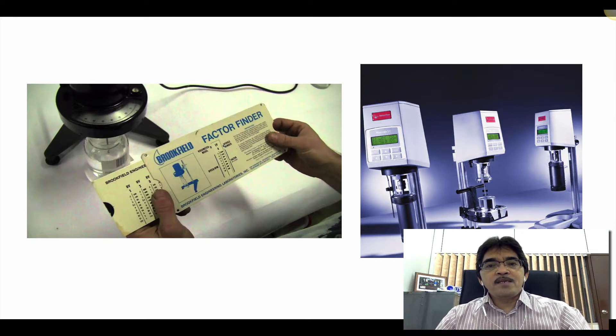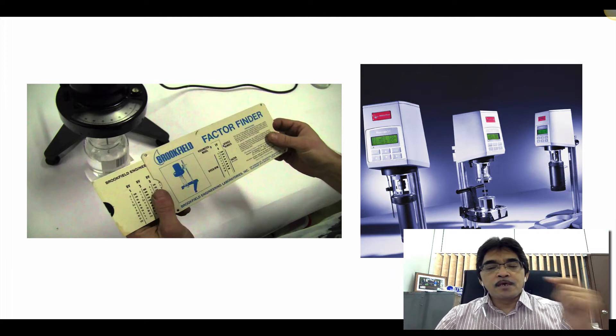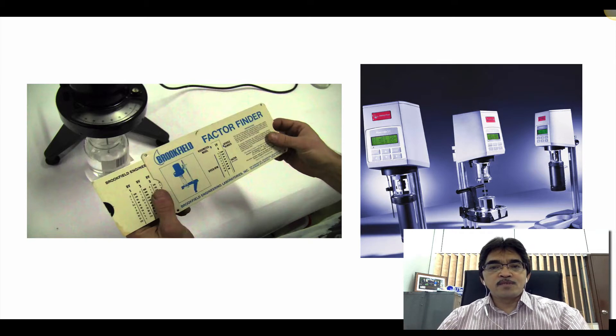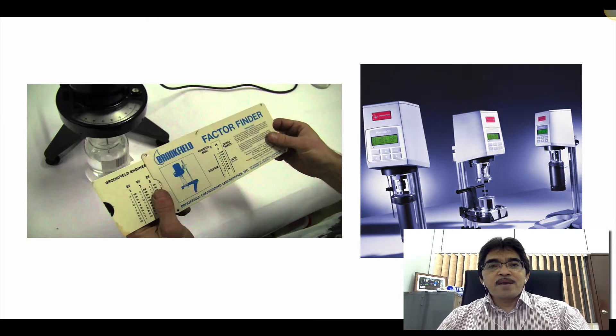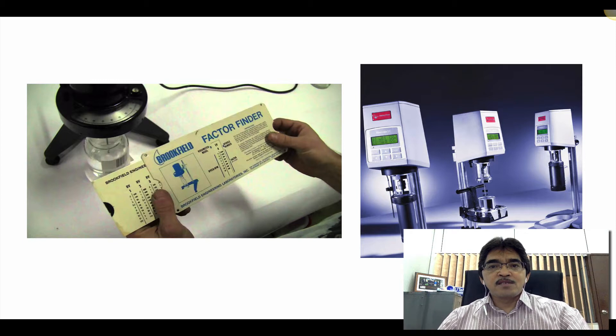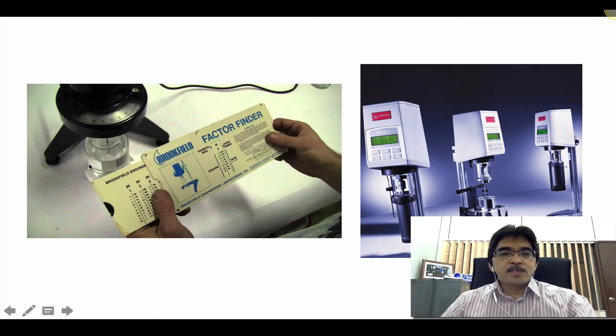We have many different ways of measuring viscosity. We can use a simple empirical method, for example, we can use the consistometer, where we measure time when we let the sample flow, then we can use a conversion factor to change that to a kinematic viscosity. Or we can use a capillary glass viscometer. That is an empirical measurement of viscosity where we cannot express the viscosity using a fundamental unit, such as pascal second or centipoise. But we can use instruments such as a Brookfield viscometer, where we can measure the sample using a different spindle.